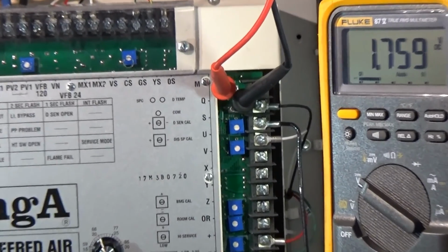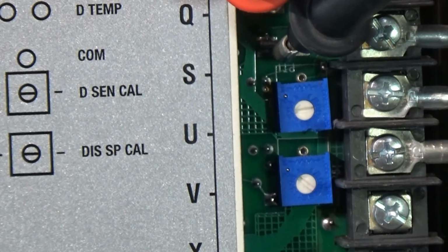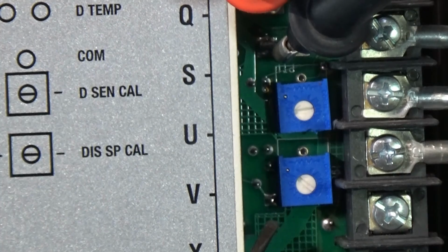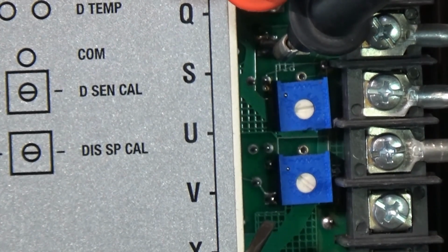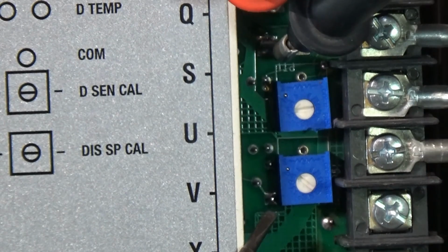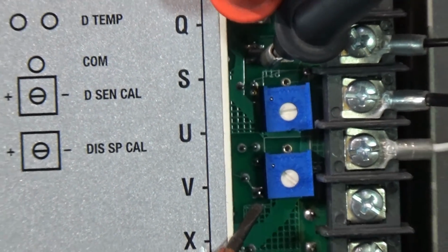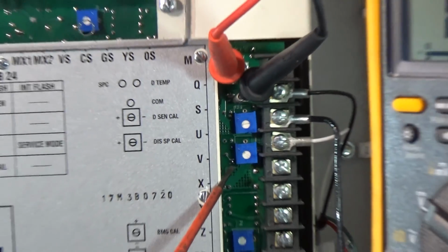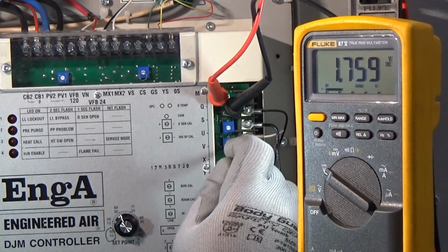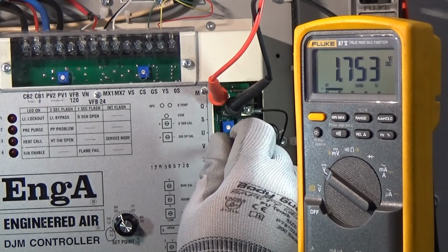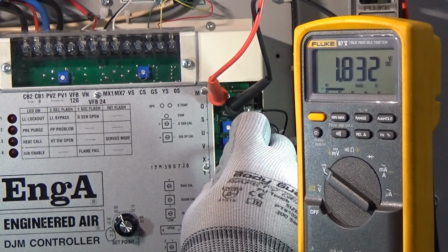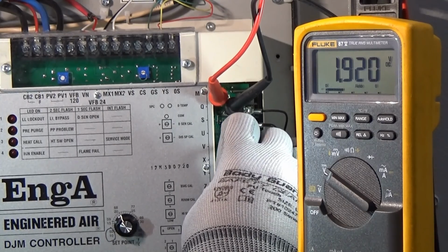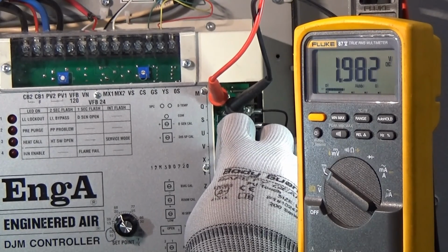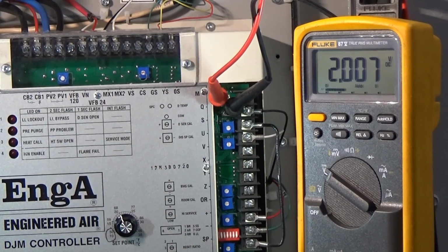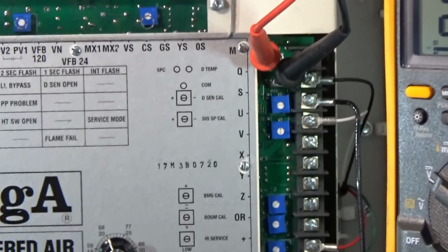To calibrate the setpoint, you will have to adjust the blue pot labeled DIS SP Cal. This pot is the second pot located below the common test pin. With your pocket screwdriver, turn the pot slowly until the reading on your meter matches the setpoint dial. Now your meter reading and your dial match, your set point is calibrated.